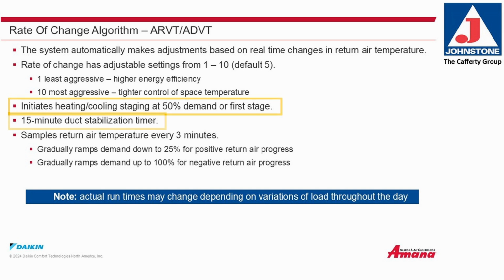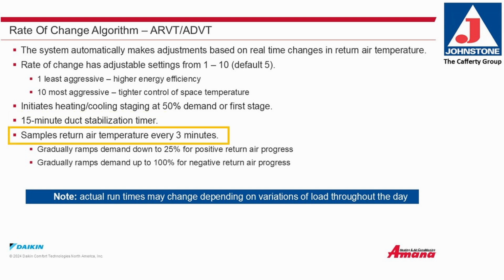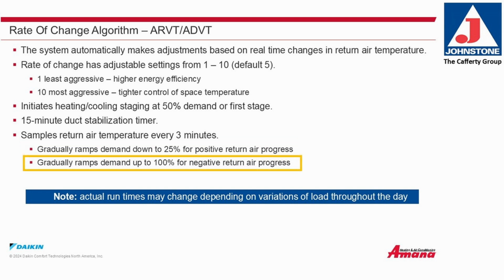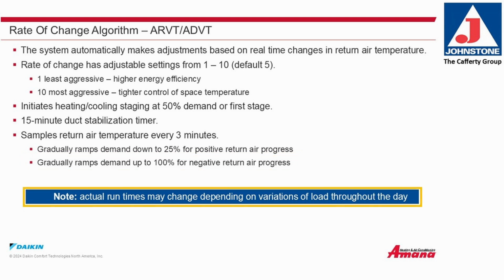15-minute duct stabilization timer. Samples return air temperature every 3 minutes. Gradually ramps down to 25% for positive return air progress, and gradually ramps up to 100% for negative return air progress. Actual run times may change depending on variations of load throughout the day.